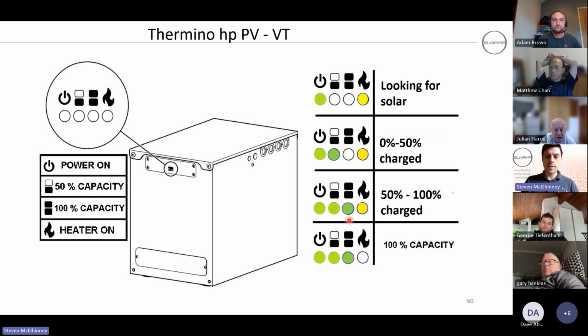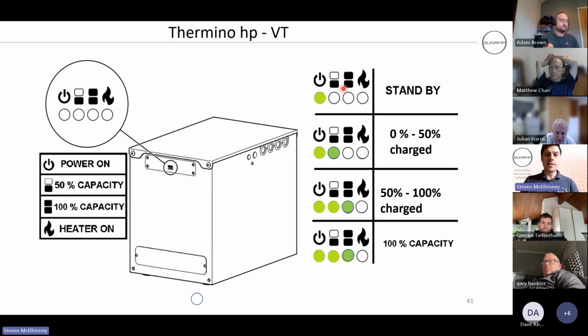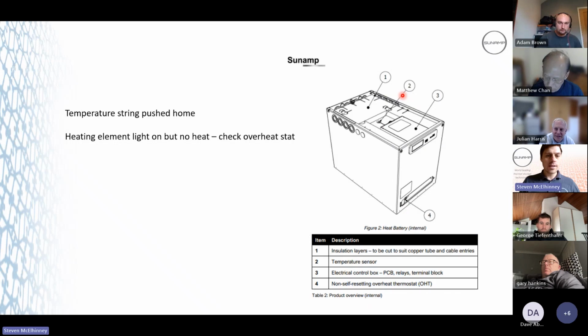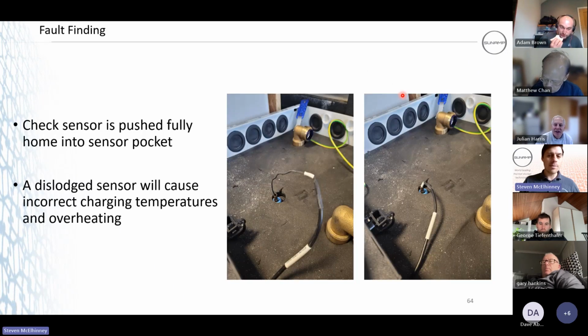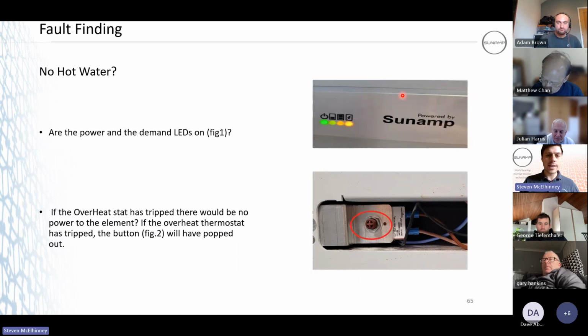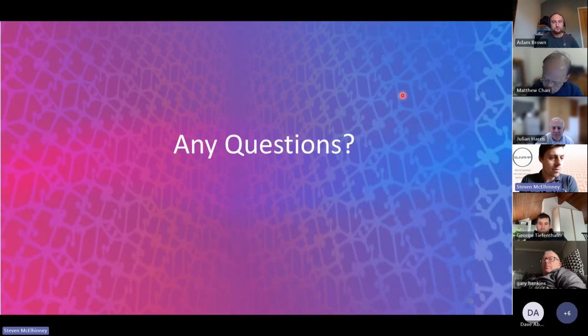So, bit of advice for your customers. Your standard Valiant, that element LED will be off all the time unless you've enabled that volt-free element control circuit. So again, if that's on and you've got the standard Valiant HP-VT, you know there's a problem with the control circuit for the element. You get your flashing lights to get a full charge. Yeah, it's the same thing as the previous ones, guys. There's not much more to talk about with the fault finding.